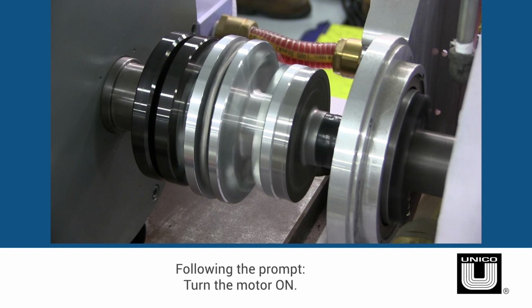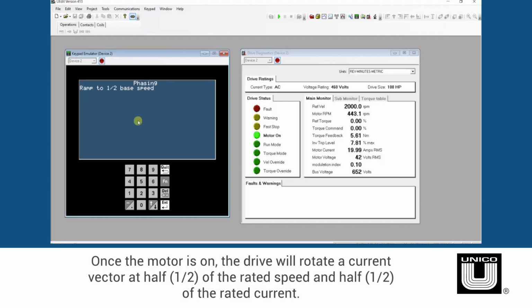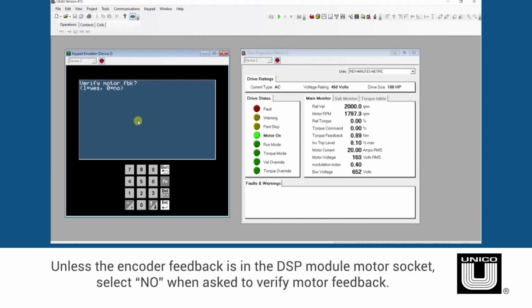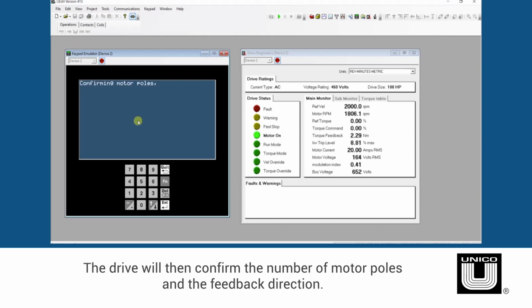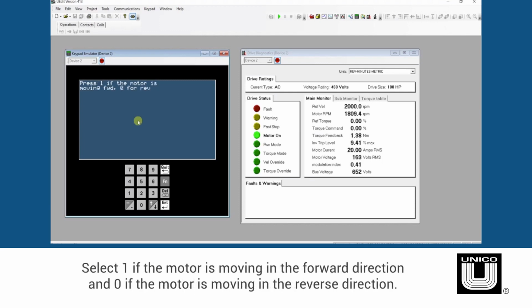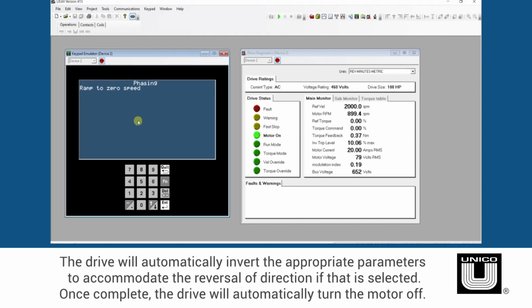Once the motor is on, the drive will rotate a current vector at 1/2 of the rated speed and 1/2 of the rated current. Unless the encoder feedback is in the DSP module motor socket, select No when asked to verify motor feedback. The drive will then confirm the number of motor poles and the feedback direction. Select 1 if the motor is moving in the forward direction, and 0 if the motor is moving in the reverse direction. The drive will automatically invert the appropriate parameters to accommodate the reversal in direction if that is selected.